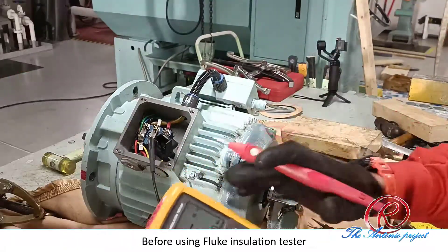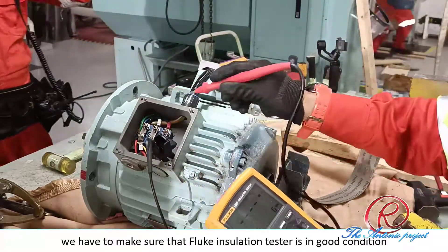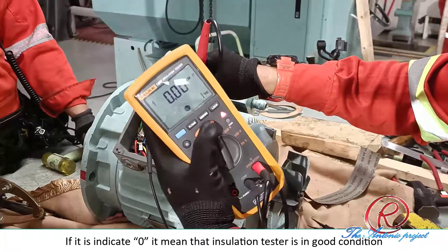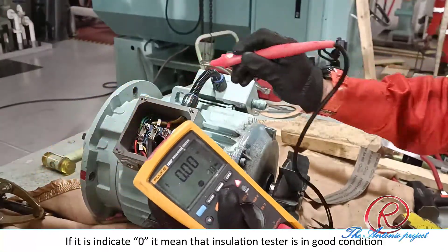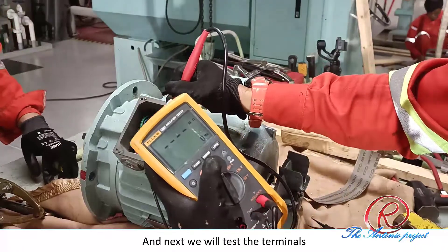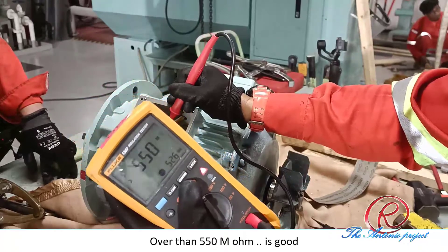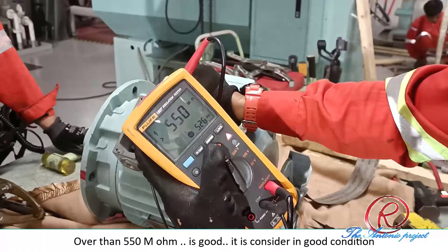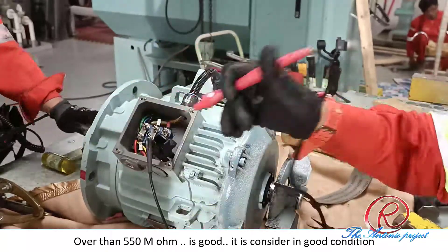Before using the Fluke insulation tester, we have to make sure that this Fluke insulation tester is in good condition by testing the body. If the indicator is at zero, it means this insulation tester is in good condition. Next we will test the terminal — 550 megaohms and over is good. So it is in good condition.